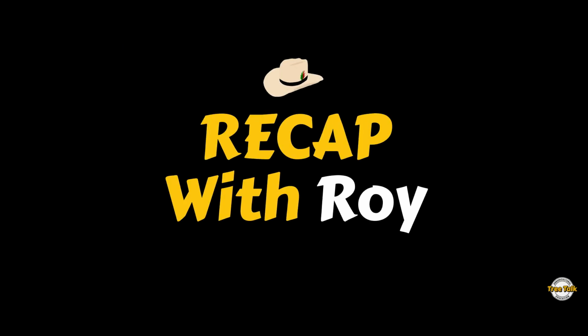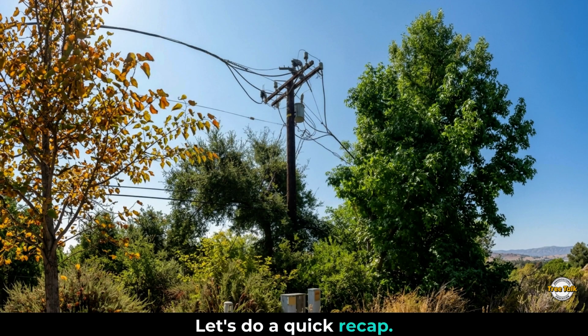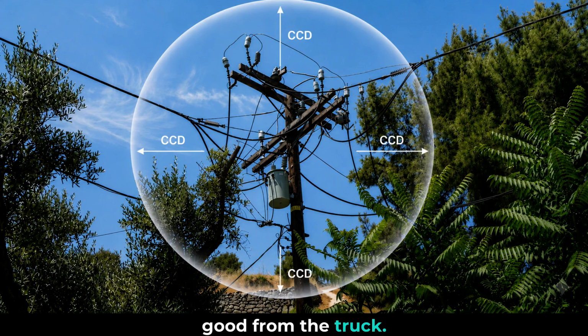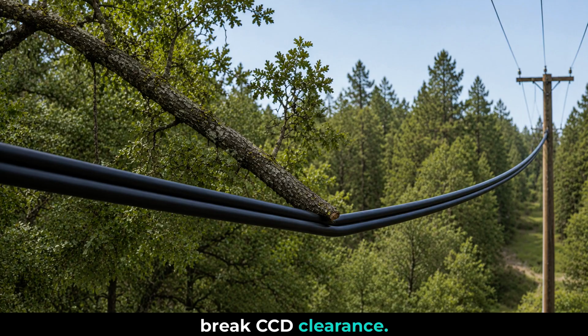All right, y'all, it's Roy. Let's do a quick recap. Now listen, it's like this. When you're patrolling aerial cable, walk the line, eyes on every pole. Don't skip one 'cause it looks good from the truck. Trim any vegetation around the poles, exposed hardware, and transformers if it'll break CCD clearance. Look for strain or abrasion on the cable. That's it. Simple as pie.